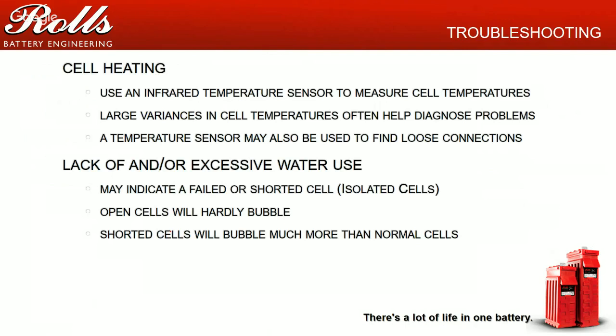I had a site I went to, must have been 6-7 years ago now. The customer had two parallel strings, and one string's specific gravities were all 1260, 1270. Great. The second string, all the specific gravities were 1220, 1230. Turned out that one of the connections had loosened up and had welded.